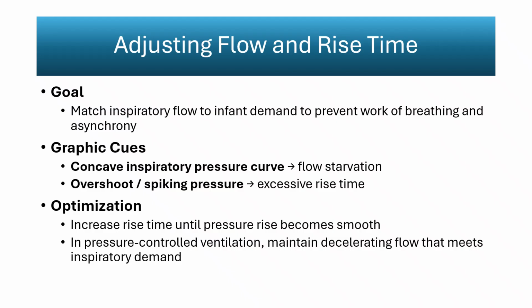Matching inspiratory flow to the infant's demand is central to preventing avoidable work of breathing and minimizing dyssynchrony. On the pressure time waveform, inadequate flow delivery appears as a concave rise during inspiration. This shape reflects the ventilator's inability to meet the infant's inspiratory effort, resulting in negative intrathoracic pressure swings and unstable ventilation. In contrast, an excessively rapid rise time produces a sharp overshoot or spike at the start of inspiration, indicating that flow is being delivered faster than the infant can comfortably accept.